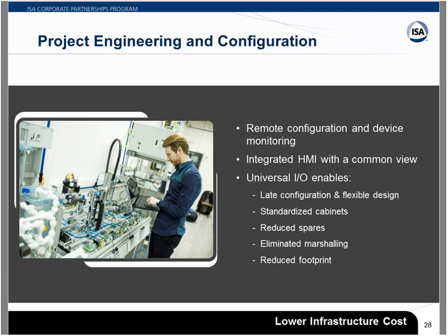I'm sure a lot of you have been through RFPs and RFQs, trying to generate or respond to those, and there's always like a 10 or 20% spare requirement. So if you move to a universal I/O technology or software configurable I/O, you don't need that extra 10-20% of a specific analog input card or digital input card. You're able to combine that into a fewer number of universal I/O cards.